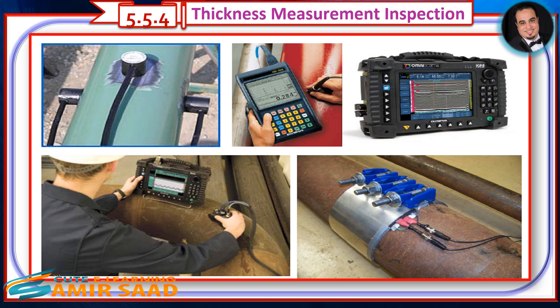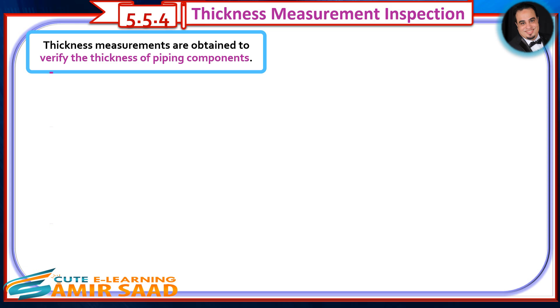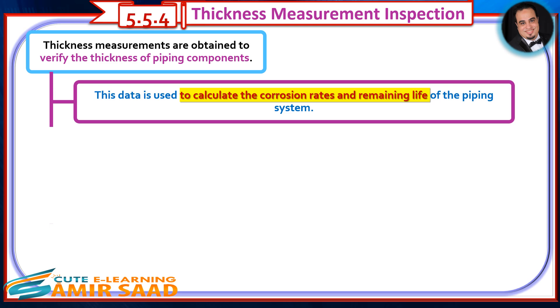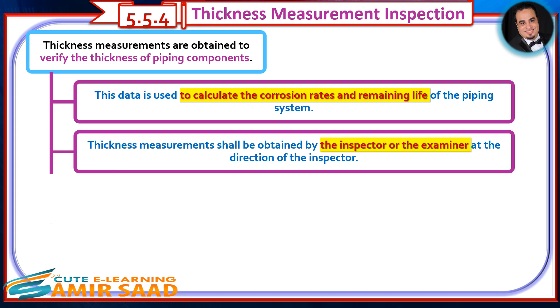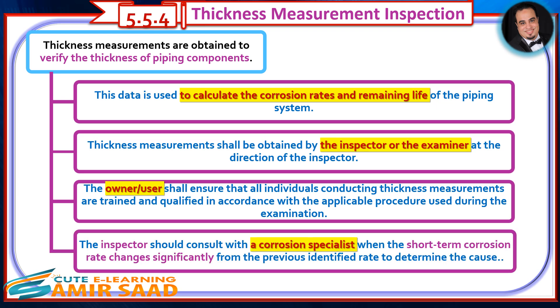Thickness measurements are obtained to verify the thickness of piping components. This data is used to calculate corrosion rates and remaining life of the piping system. Thickness measurements shall be obtained by the inspector or examiner at the direction of the inspector. The owner-user shall ensure that all individuals conducting thickness measurements are trained and qualified in accordance with the applicable procedure. The inspector should consult with a corrosion specialist when the short-term corrosion rate changes significantly from the previously identified rate to determine the cause.